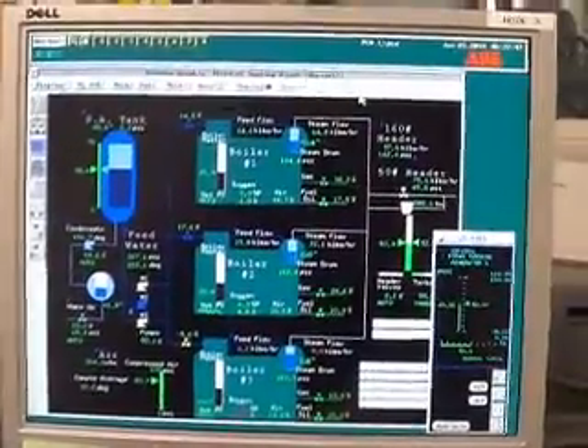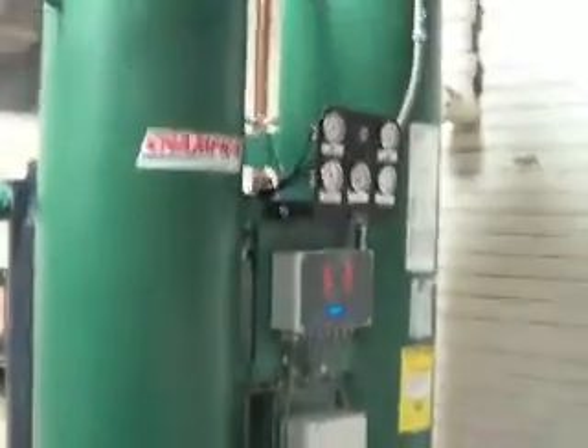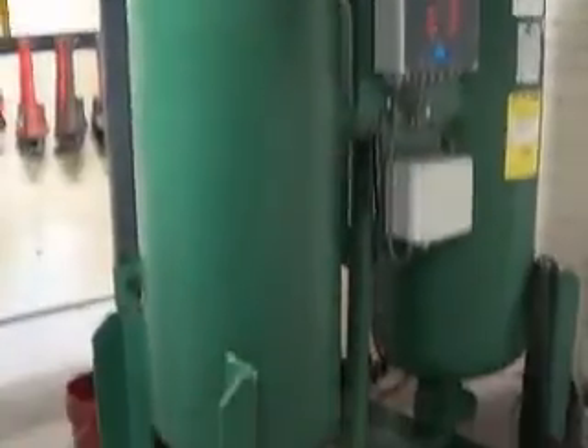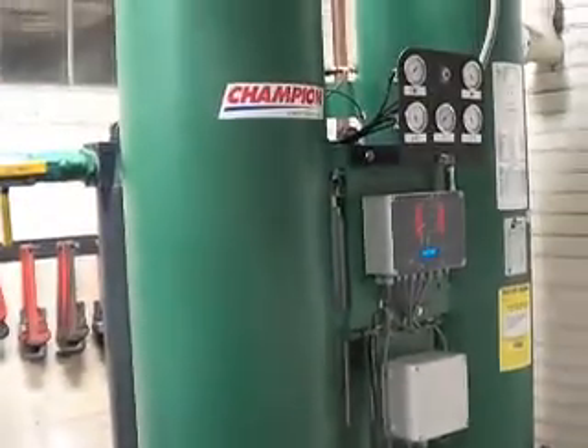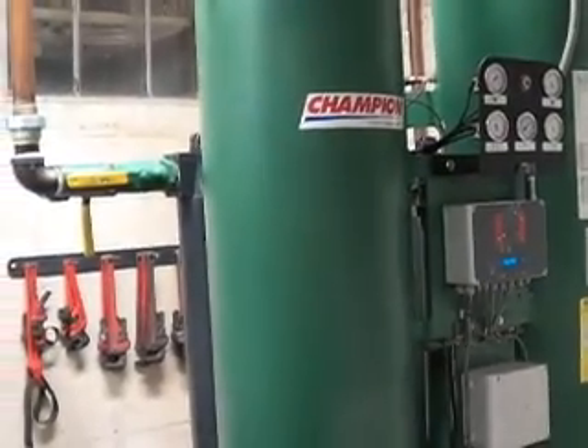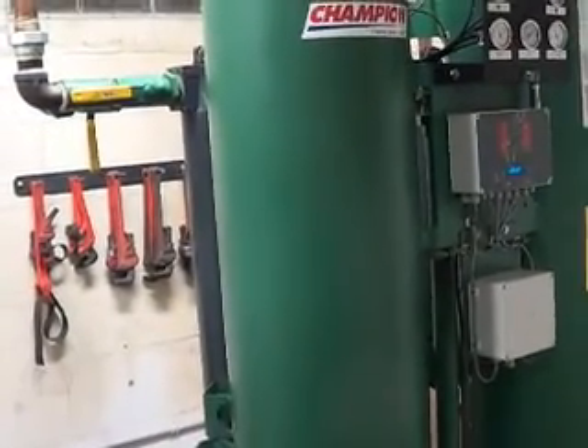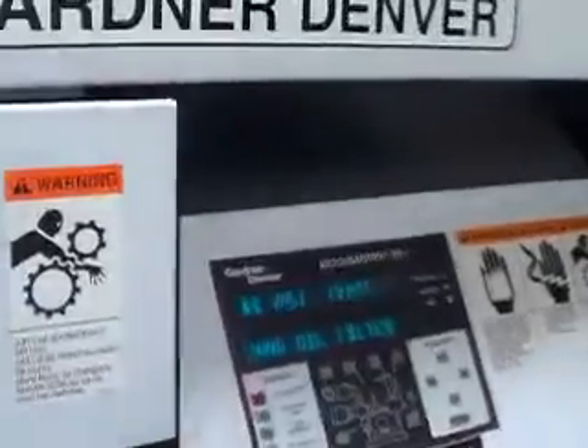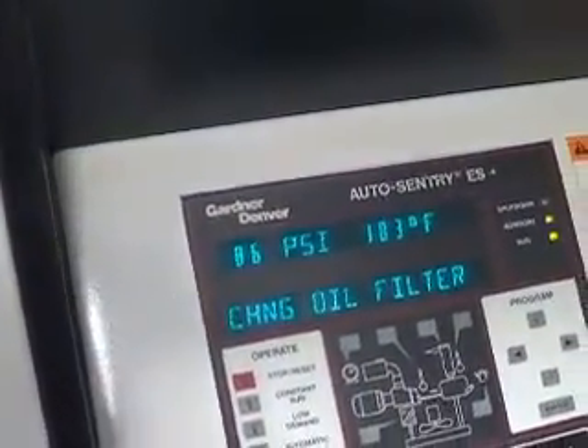This is not the way I expected to start the new year. But I'll take you on a quick round of the plant, show you what exactly we do and what I'm looking for. Right here, these are a desiccant air dryer, and it is to dry the air that we use throughout the plant for control. Here's the one that's carrying the load right now, 183 degree water.